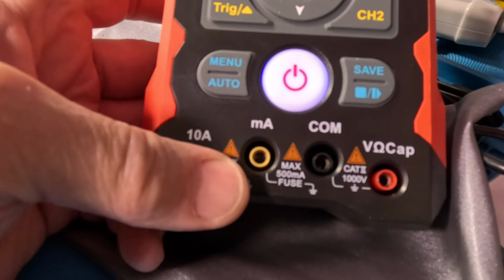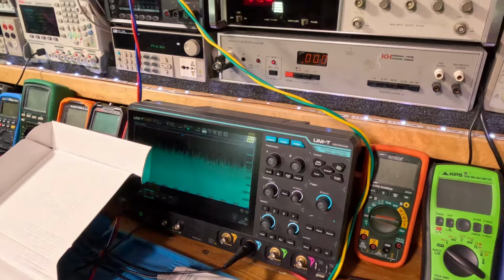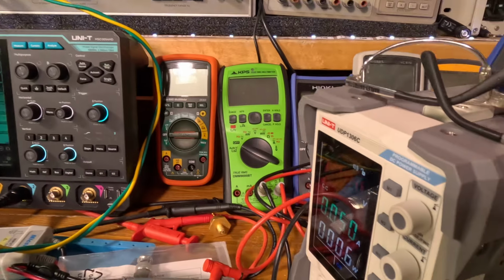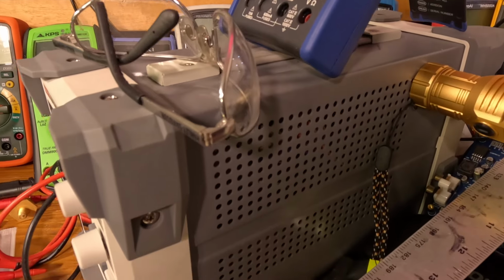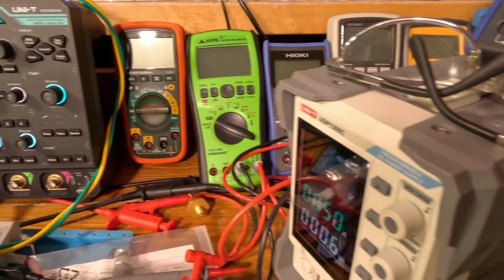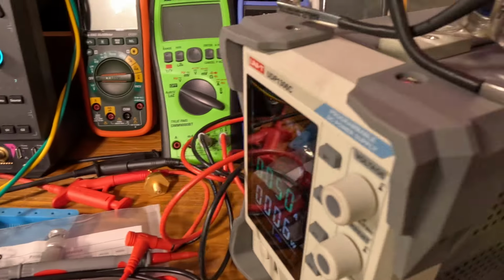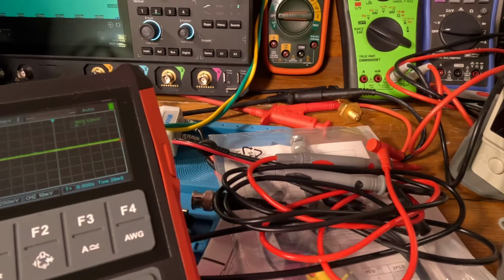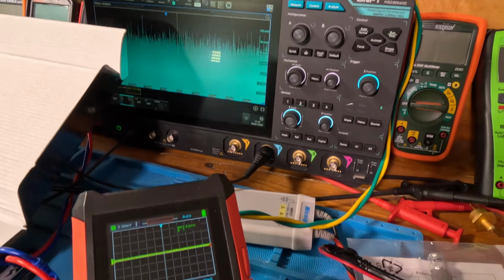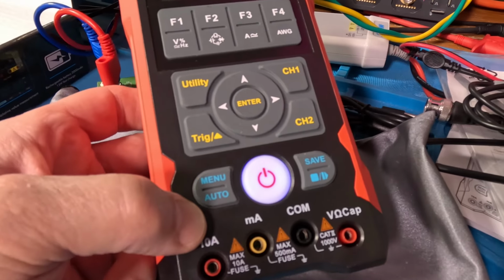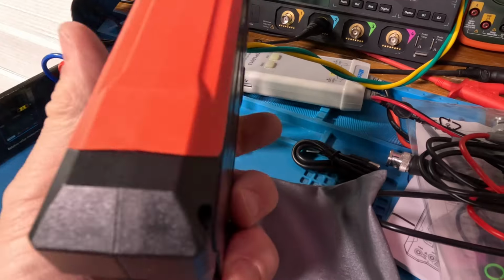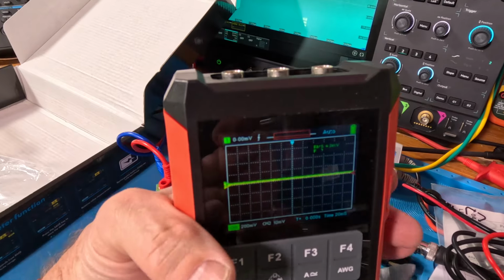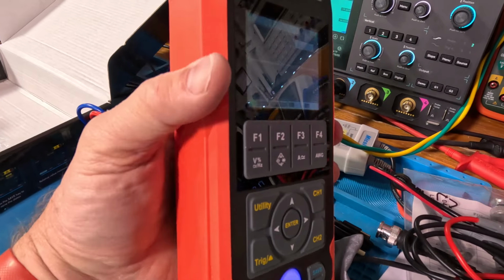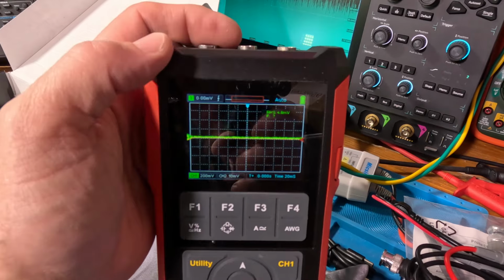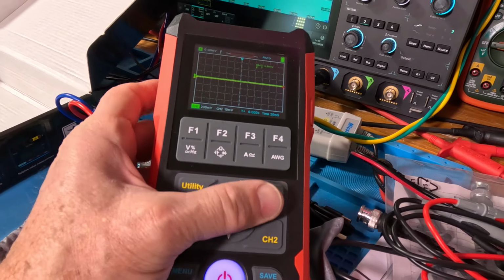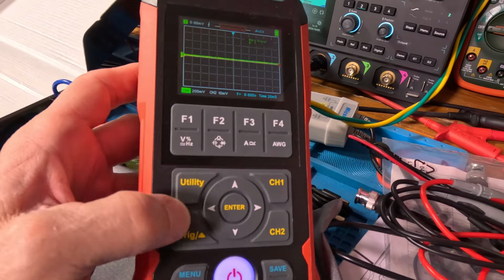So category 1 and 2 is just stuff here at the bench. If I want to open up something and probe around inside, even though it's 120 volts here in the US, it's still considered category 2 because there's not a lot of energy, since there's a 15 amp breaker at the very least that's going to pop. So there we go. Now just to give you an idea of the case, it's a big case. On the side, this orange stuff is rubberized. Everything else is hard plastic. These buttons are all rubberized too.